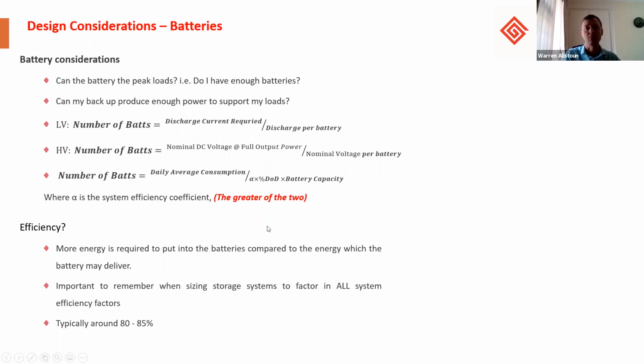Then we also need to consider efficiency. So let's, for example, say we've got a 10 kilowatt hour battery. For the battery to deliver 10 kilowatt hours, of course, we'll need to put in more than 10 kilowatt hours because it's not 100% efficient. So we need to consider this when deploying systems. It's the round trip efficiency, which is the amount of energy put in, amount of energy put out over the rated capacity. Again, typically around 80 to 85%.